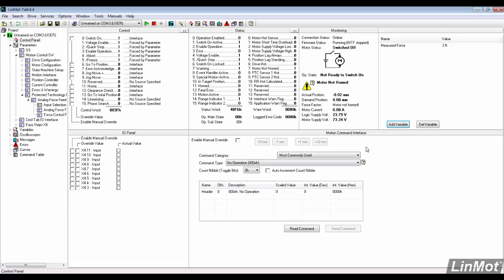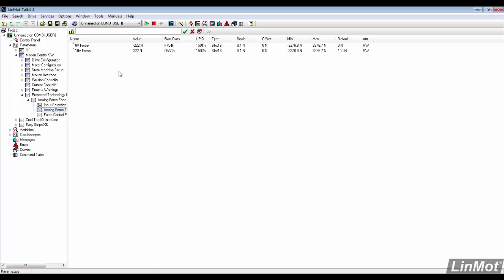The load cell is reading a force of 3 Newtons with nothing acting on it. We can go back and adjust the 0 and 10 volt values to make the load cell read closer to 0.